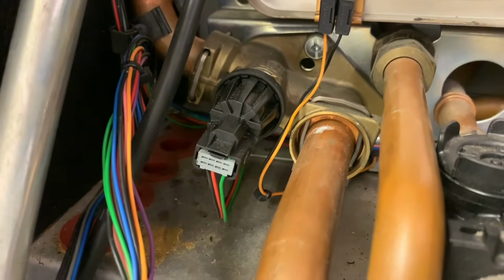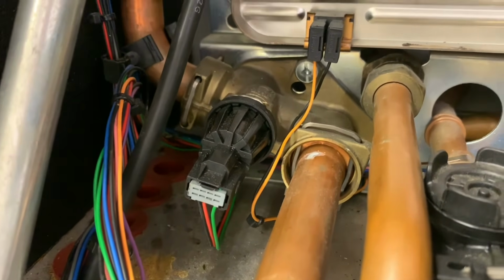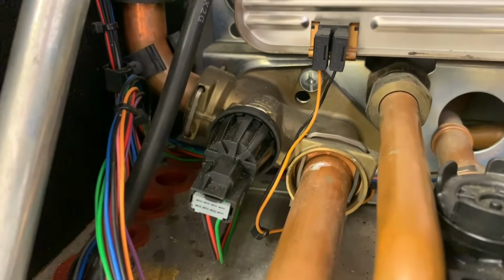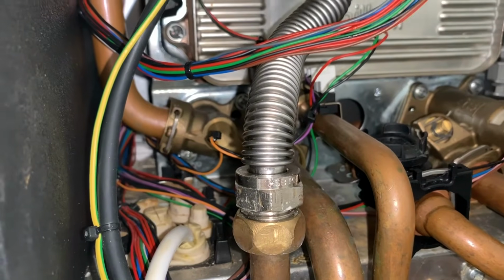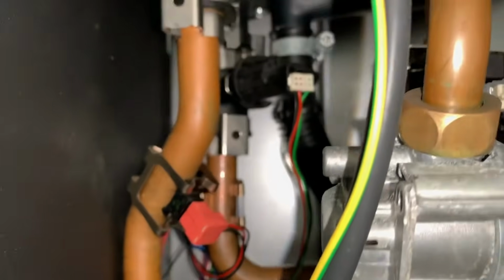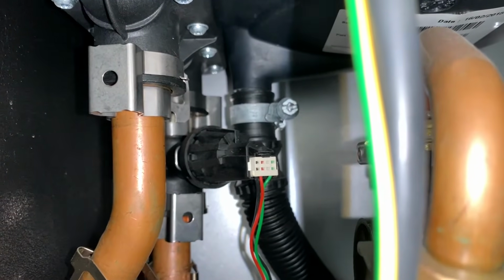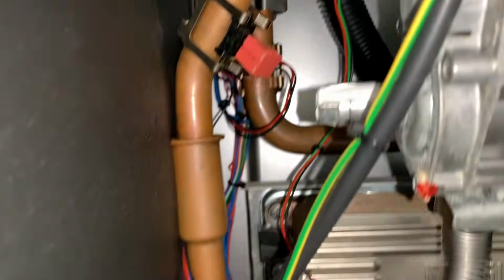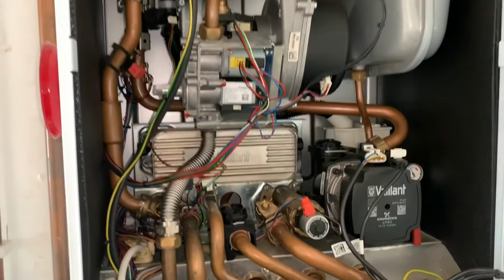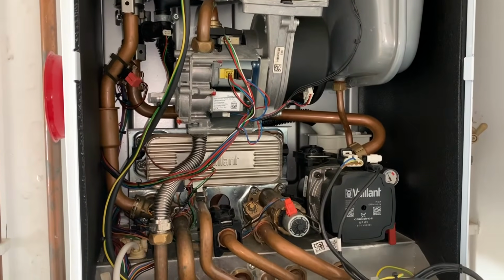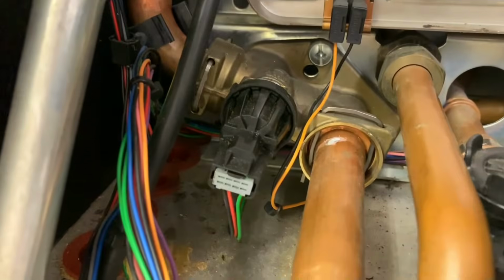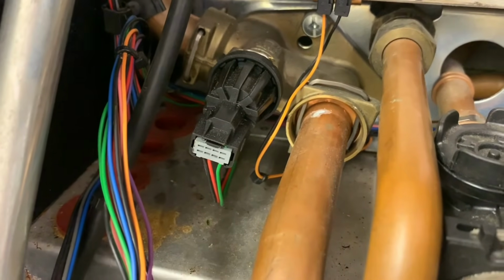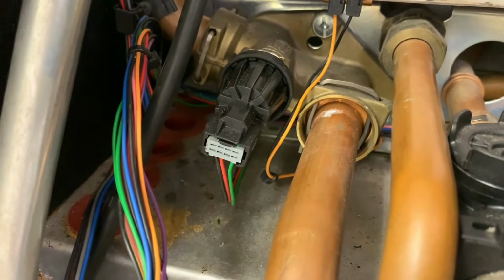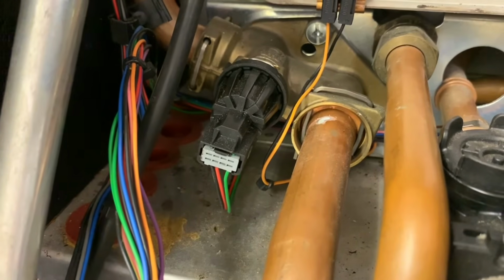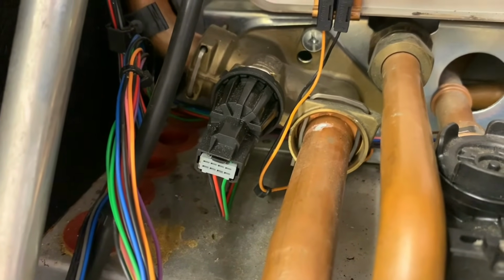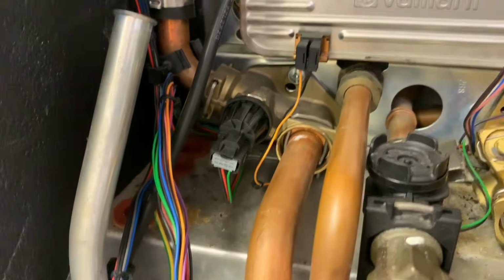I think they've had about 3 series of them. And they're that troublesome, blocking up with, again, dirty systems. Vaillant moved them to the top up here. So they're now, this is the flow, this is the return. I'm almost certain they're on the return, but I might be wrong, but I think they're on the return. Because what this also does, as well as low water pressure, it also proves the pump's working and it also gives you your digital display for your pressure reading. So kind of 3 things in one.